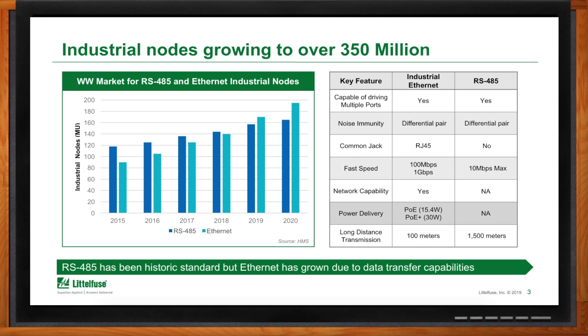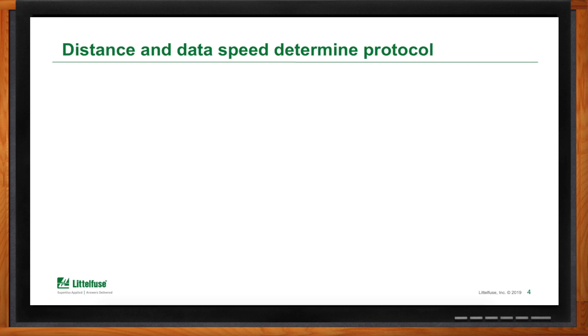Ethernet runs at a faster speed — up to 1 gigabit per second — while RS-485 is limited to 10 megabits per second. Ethernet also has the ability to do Power over Ethernet, which powers the field device. RS-485, on the other hand, has the ability to transmit longer distances — up to 1,500 meters — while industrial Ethernet is limited to 100 meters.